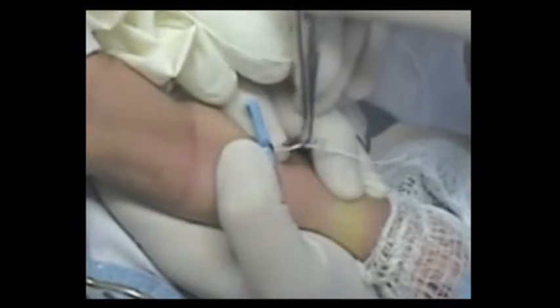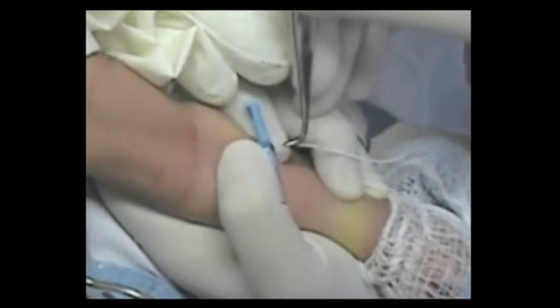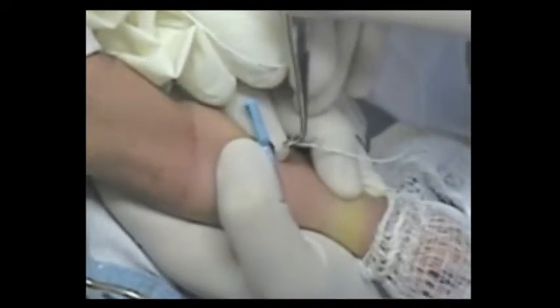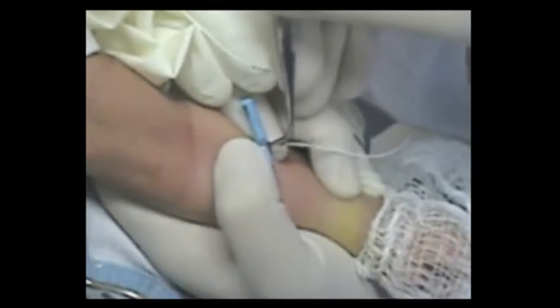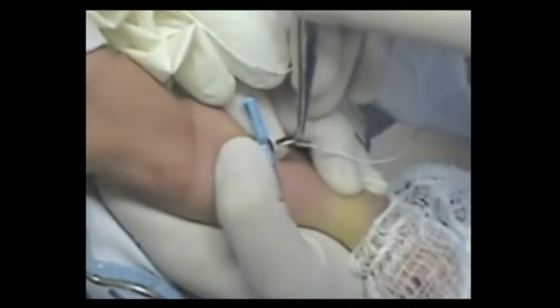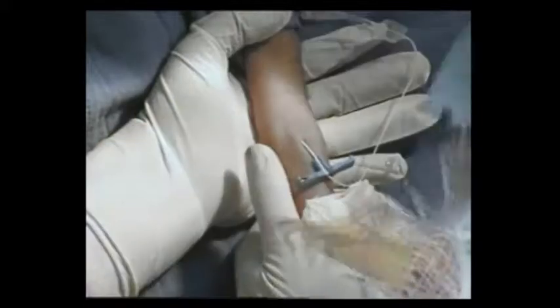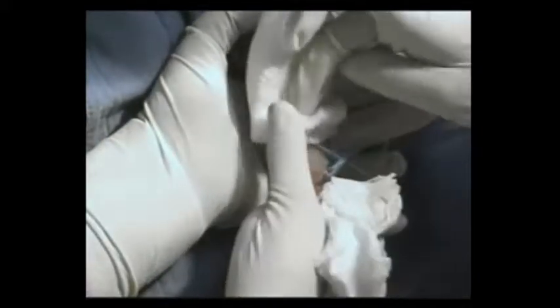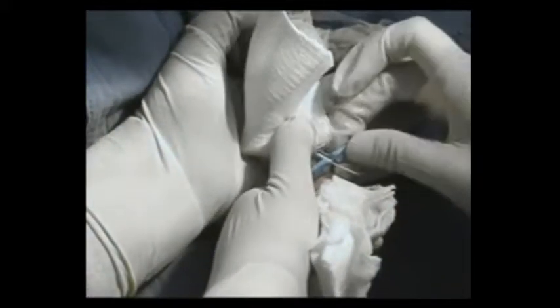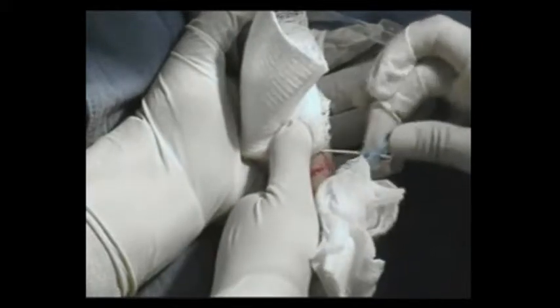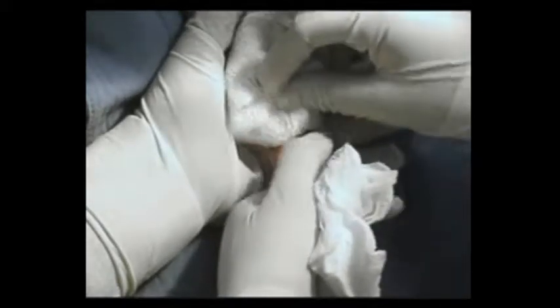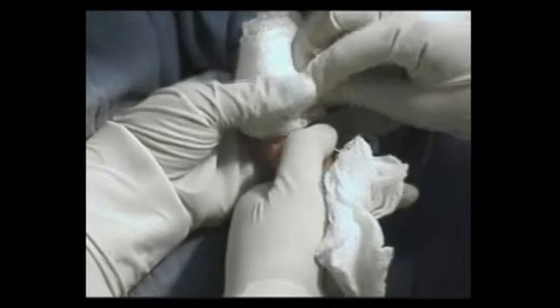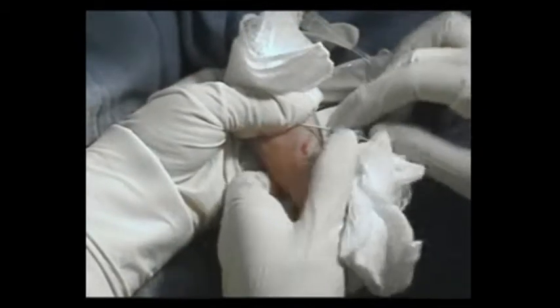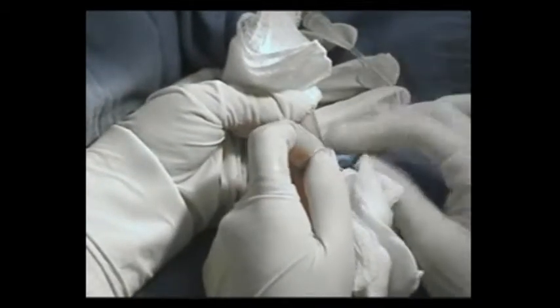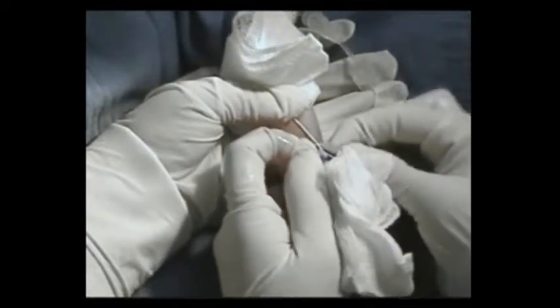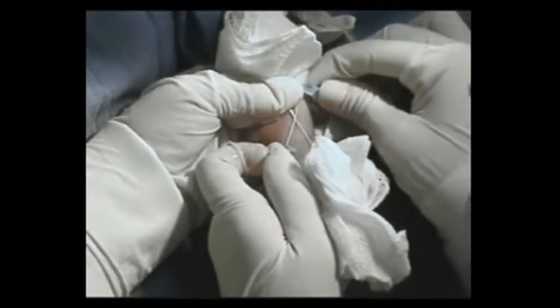Keep the strip extended. With the forceps of the mini equipment, carefully introduce the catheter to the calculated length without forcing. To avoid the catheter taking a cephalic direction, we recommend during the fixation of the patient to turn the head to the side of the puncture. Holding the catheter on the skin of the patient, take off the sheath.